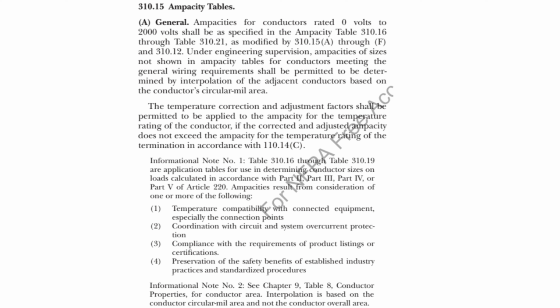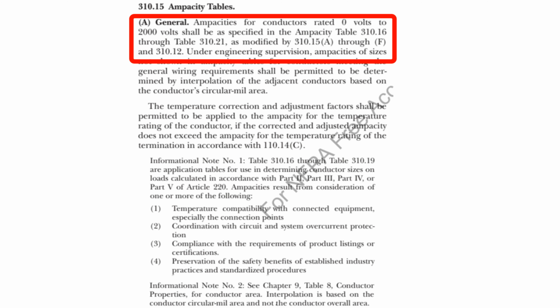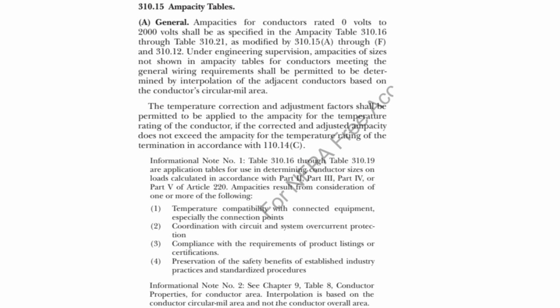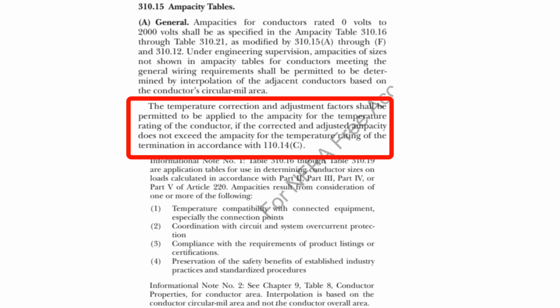Article 310.15 covers the ampacity tables. Starting at the top, A. General. Ampacities for conductors rated 0 to 2000 volts shall be specified in the ampacity table 310.16 through table 310.21, as modified by 310.15(A) through (F) and 310.12. I'll skip over the part about engineering supervision because it doesn't apply here. Next, the temperature correction and adjustment factors shall be permitted to be applied to the ampacity for the temperature rating of the conductor if the corrected and adjusted ampacity does not exceed the ampacity for the temperature rating of the termination in accordance with 110.14(C).